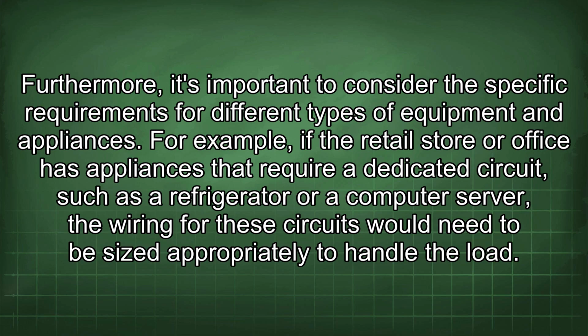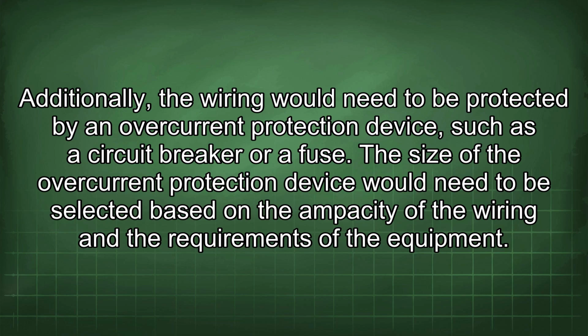Furthermore, it's important to consider the specific requirements for different types of equipment and appliances. For example, if the retail store or office has appliances that require a dedicated circuit, such as a refrigerator or a computer server, the wiring for these circuits would need to be sized appropriately to handle the load. Additionally, the wiring would need to be protected by an overcurrent protection device, such as a circuit breaker or a fuse. The size of the overcurrent protection device would need to be selected based on the ampacity of the wiring and the requirements of the equipment.